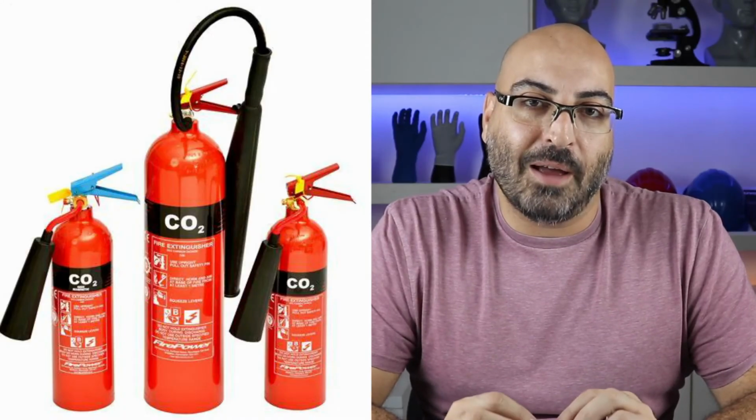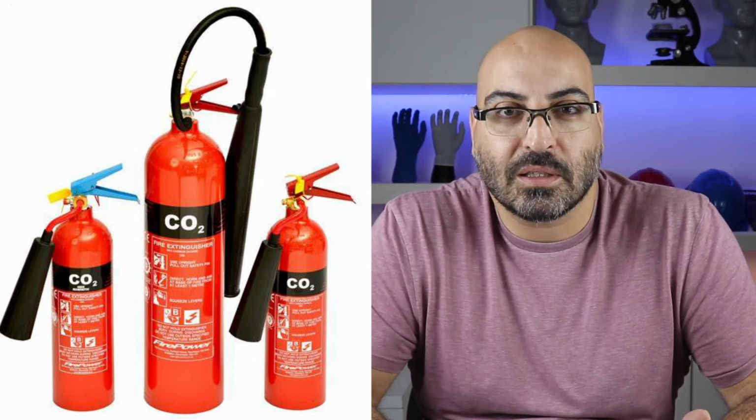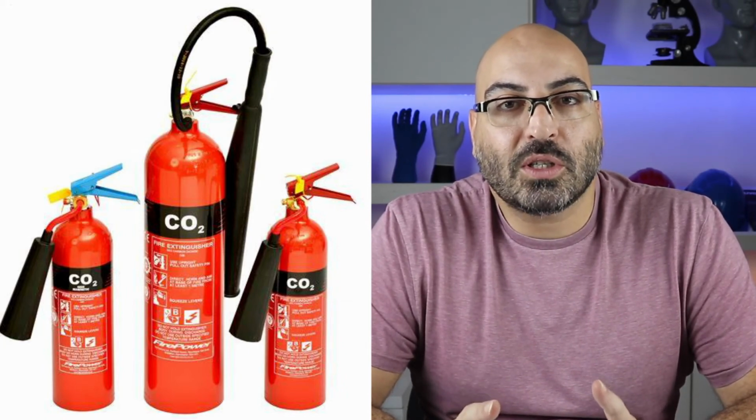The last class of fire is electrical fires, and you have to use the CO2 carbon dioxide fire extinguisher. You can use the dry powder, but only up to 1,000 volts. But who would know that? How would you know what 1,000 volts is? So rather just use the CO2 fire extinguisher. Most server rooms will have CO2 fire extinguishers.